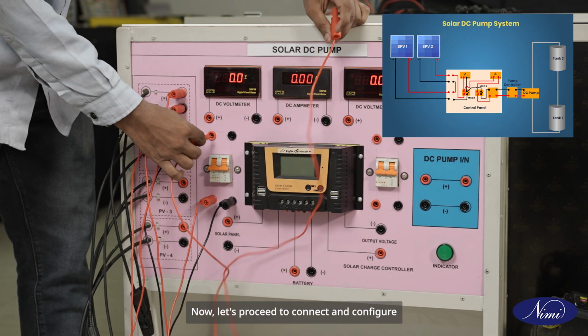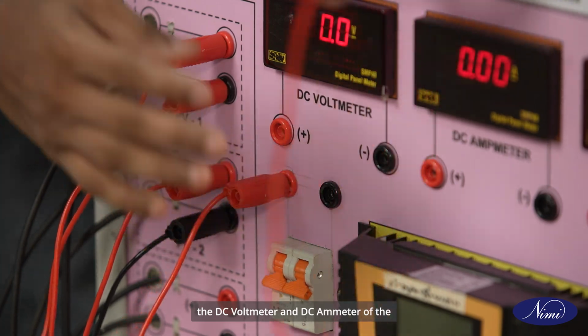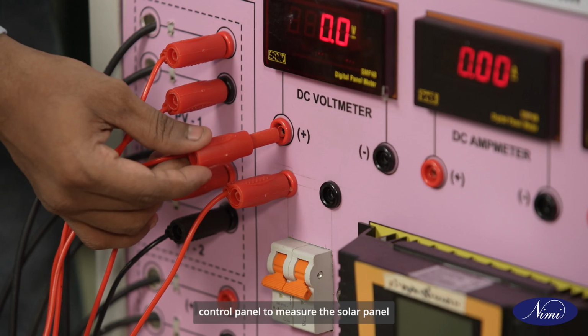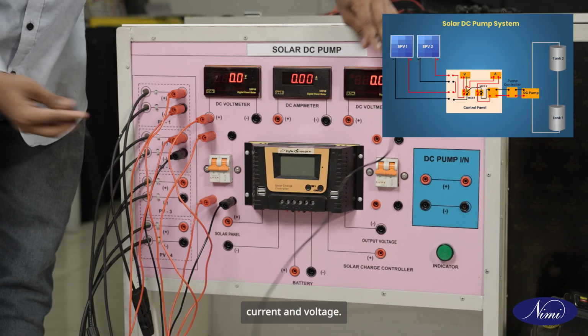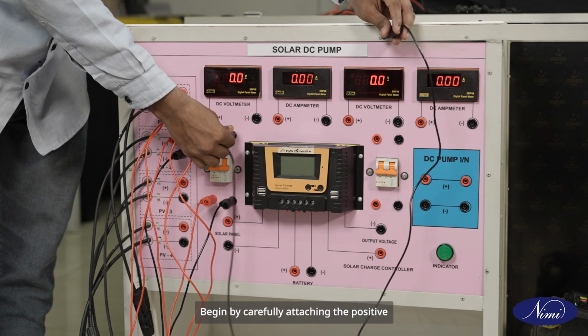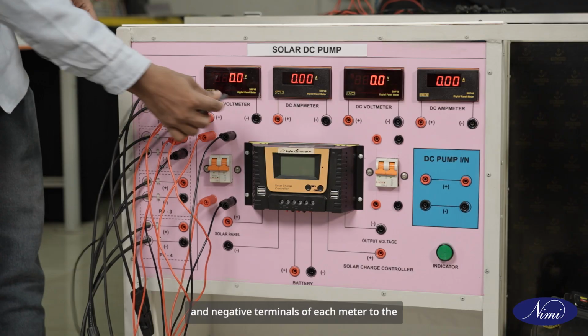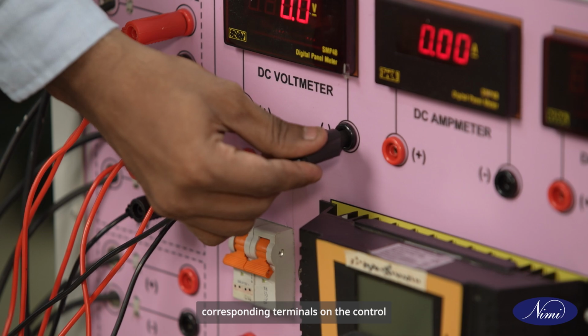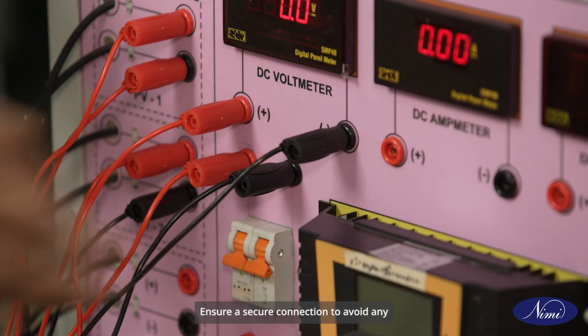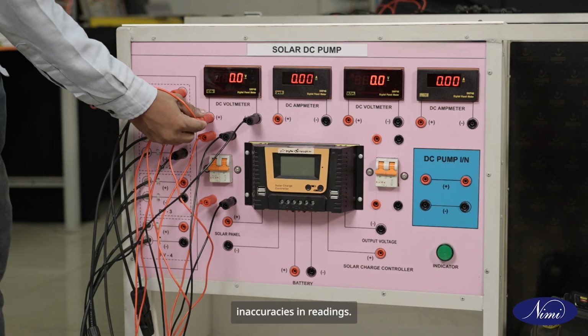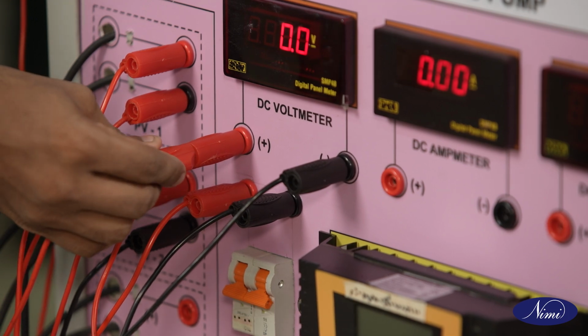Now let's proceed to connect and configure the DC voltmeter and DC ammeter of the control panel to measure the solar panel current and voltage. Begin by carefully attaching the positive and negative terminals of each meter to the corresponding terminals on the control panel, ensuring a secure connection to avoid any inaccuracies in readings.